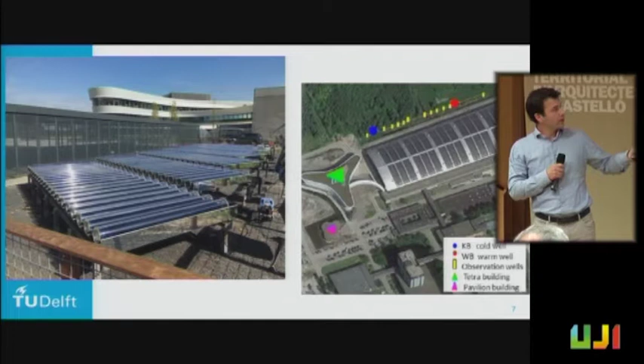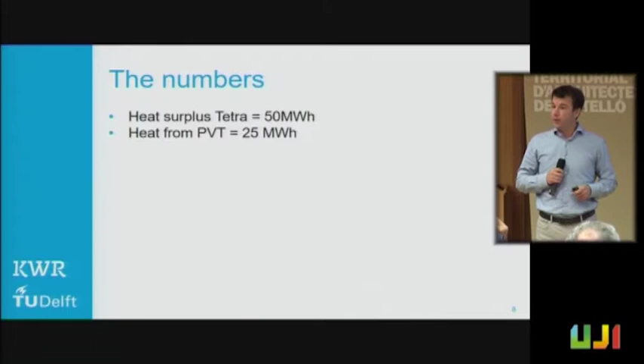Like I mentioned, office buildings in the Netherlands often have a larger cooling demand, so they have a heat surplus. After a couple of years of running the ATES system of the Tetra building, they found out that the yearly heat surplus of the Tetra building is about 50 megawatt hours. We can get another 25 megawatt hours from the PVT panels every year. So in total we can get 75 megawatt hours of heat.